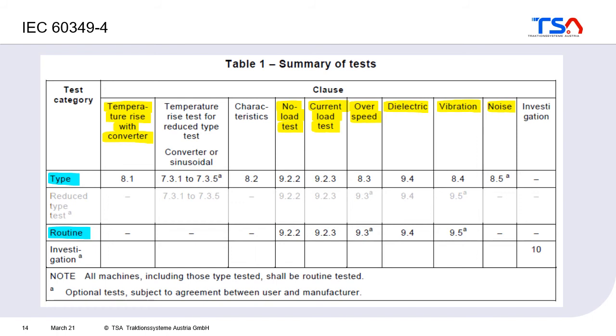As shown in the table, many tests must be performed — especially for the type test. A typical type test can take one to two weeks and is done on one machine of every new design. The routine test must be performed on every machine manufactured, so it is important that it does not take as long.